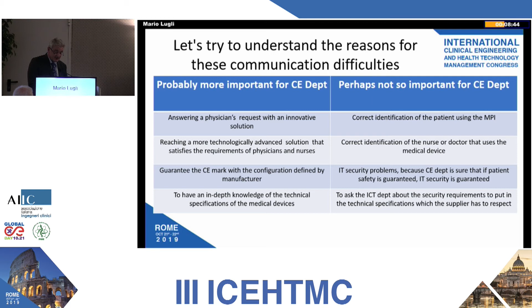For the CE department, probably it is more important to answer physicians' requests with an innovative solution, reaching a more technologically advanced solution to satisfy the requirements of physicians and nurses, guarantee the CE mark with the configuration defined by the manufacturer, and have an in-depth knowledge of the technical specification of the medical device. Less important, perhaps, is correct identification, for example of the patient using MPI, or of the nurse or doctor that used the medical device, and IT security, because CE departments are generally sure that if patient safety is guaranteed, IT security is guaranteed. It's not true. They should ask the ICT department about the security requirements to put in the technical specifications which the supplier has to respect.